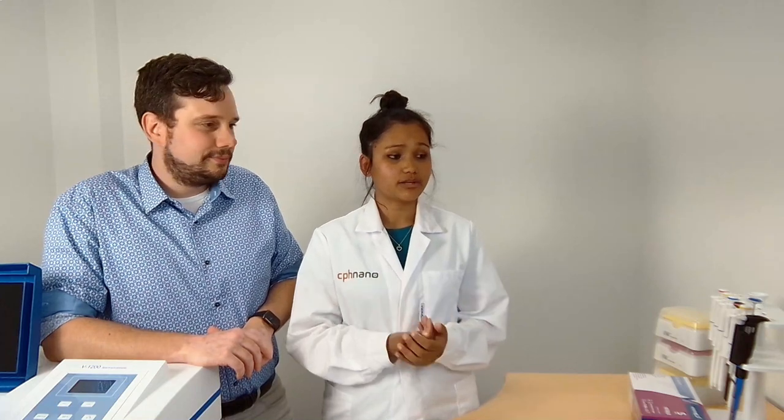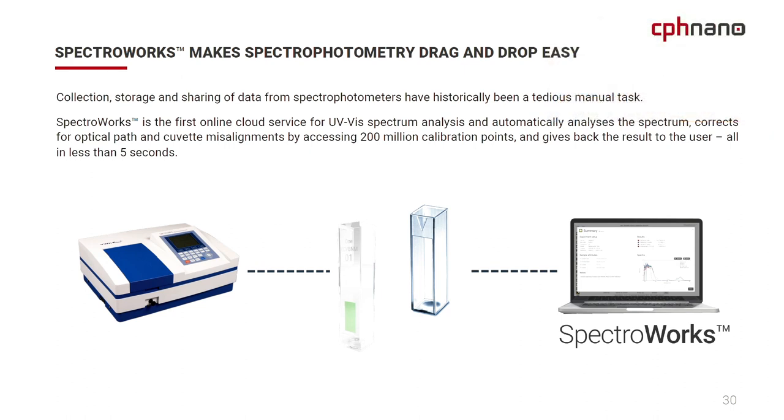Thank you, Emil, for a very nice demonstration of SpectroWorks. SpectroWorks makes spectrometry much easier with drag-and-drop functionality. Collection, storage, and sharing of spectrophotometer data have traditionally been very tedious — done manually by hand. Now, for the first time with SpectroWorks from cphnano, this cloud service for UV-Vis spectrum analysis can automatically analyze the spectrum, correct for optical path and cuvette misalignments by assessing 200 million calibration points, and return results to the user in less than five seconds.